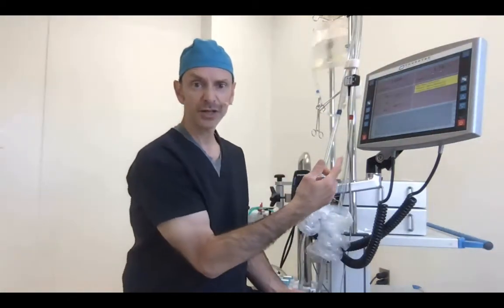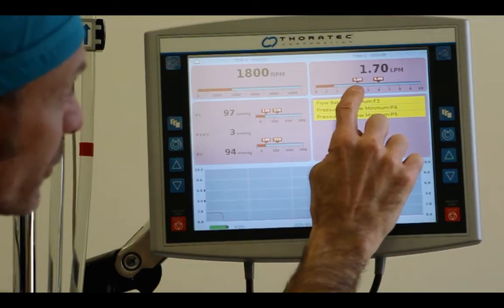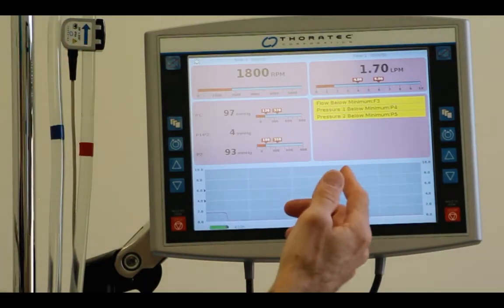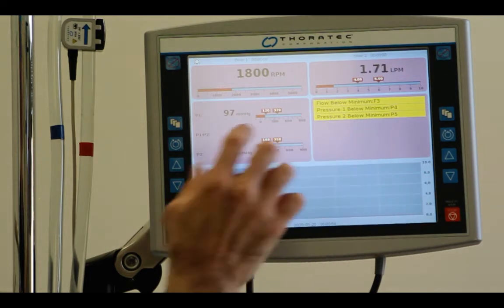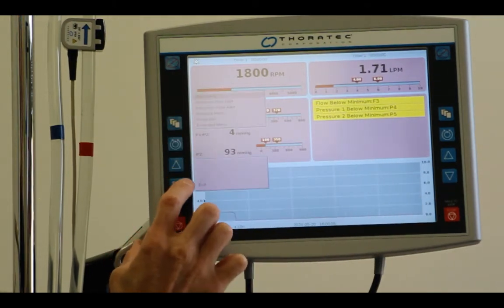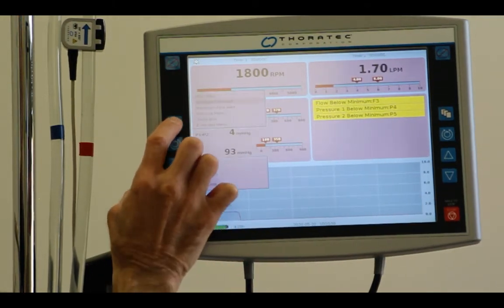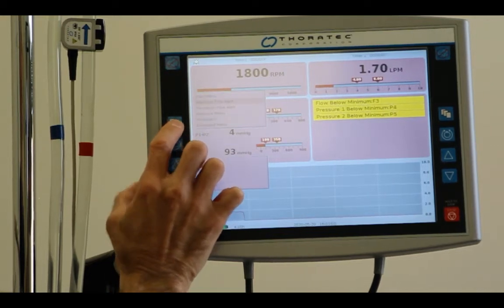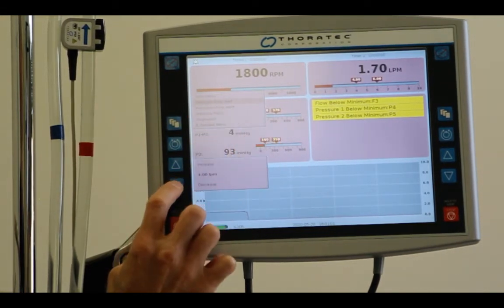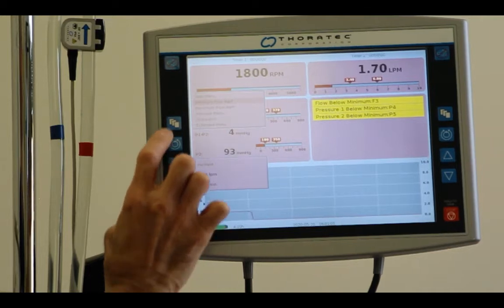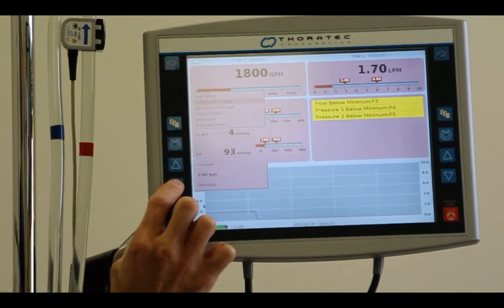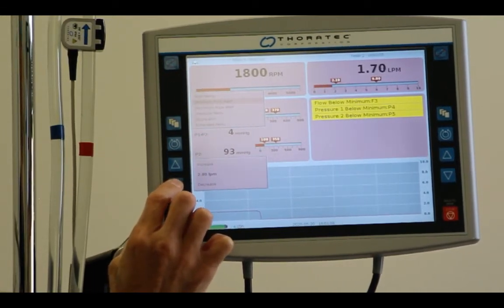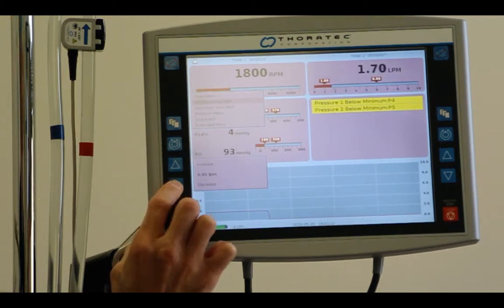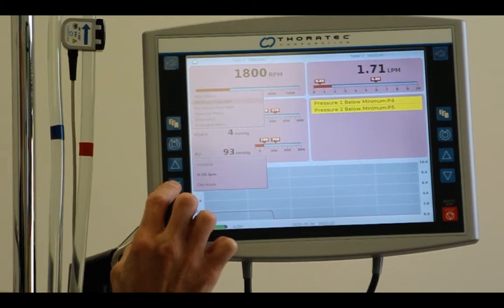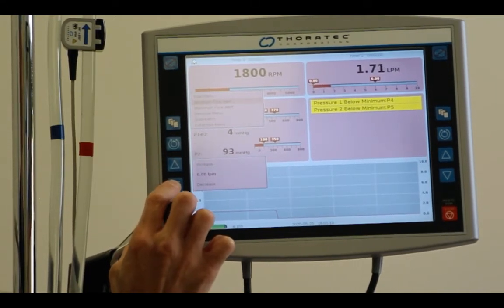Now, if we're just initiating flow for the very first time, I probably wouldn't have a bracket way up here at 4 liters a minute, because I know for the next couple minutes I'm just going to be reaching that. So let's get in there and turn that off, or it's really going to annoy us. And we'll step down to the minimum flow alert, and we'll decrease that. We'll decrease that minimum flow alert right now to essentially 0 until we get on and stabilize this patient. So your minimum flow alert is now 0.